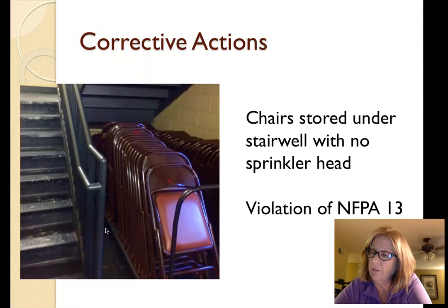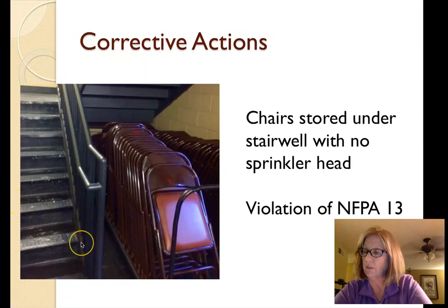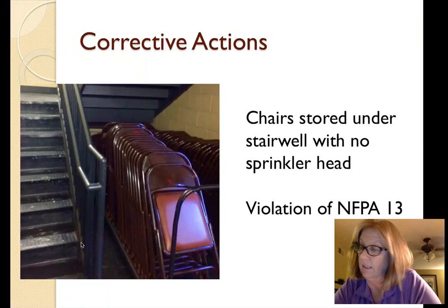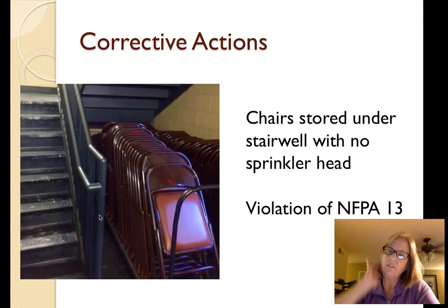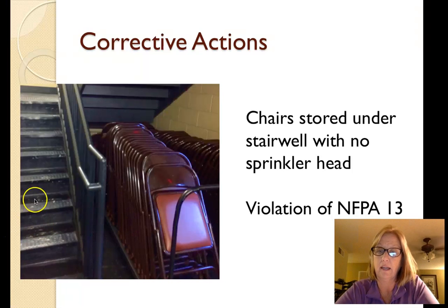On the way to the riser room on the west side of the structure, we encountered some chairs that were being stored under the stairwell. This is a violation because nothing is to be stored under a stairwell unless a sprinkler head has been installed in that location, per NFPA 13.